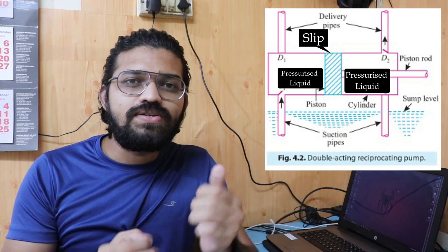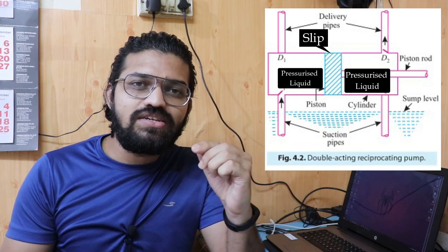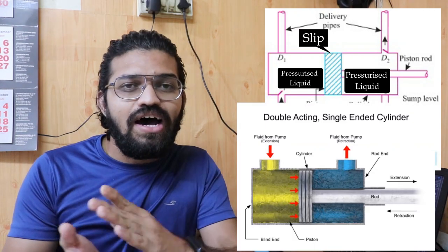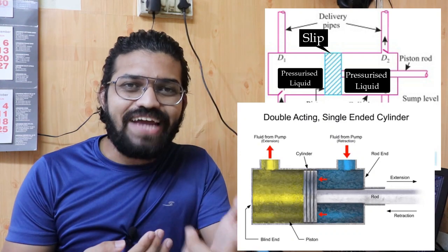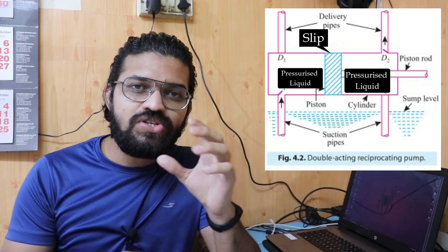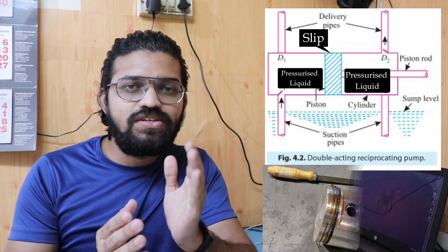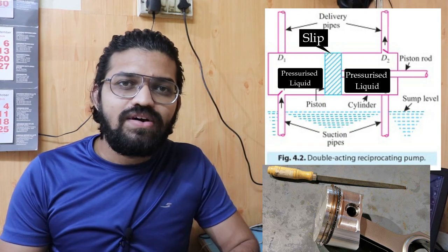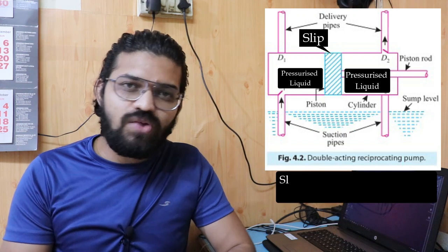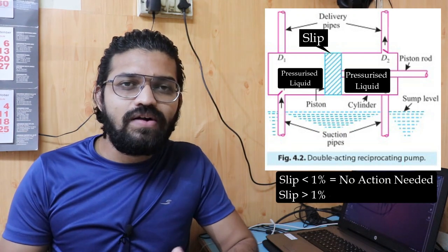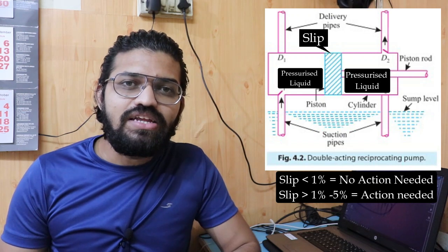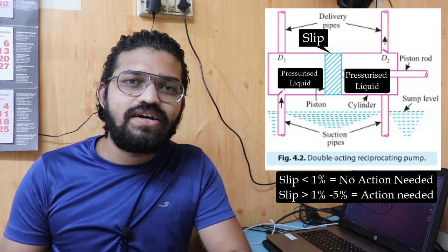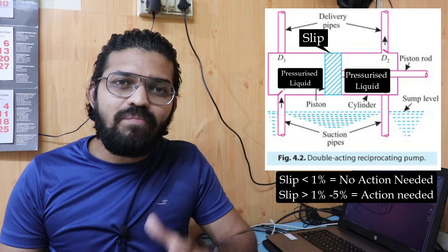Slip occurs due to wear of the piston rings or the cylinder liner rings, caused by the reciprocating motion of the piston over time. After some intervals, those piston rings and liner rings wear out and leakage — slip — occurs. If the slip in the pump is less than one percent, the pump is working absolutely fine and no further action is required. If the slip is between one to five percent, overhauling of the pump is required.